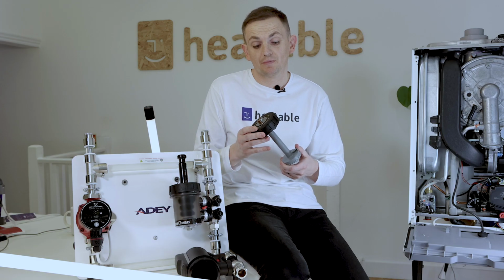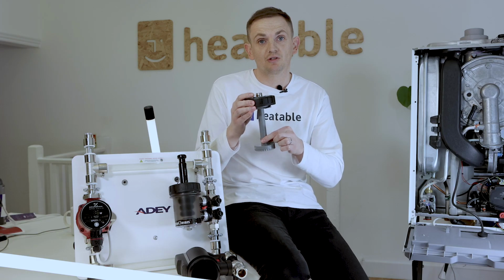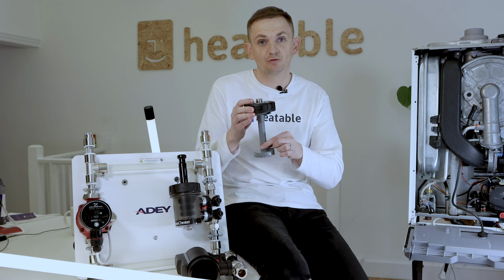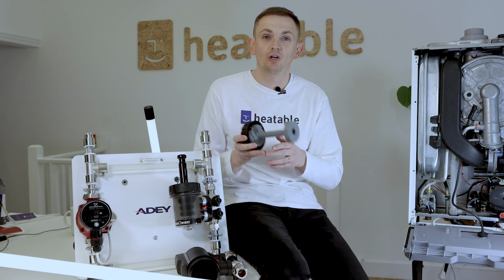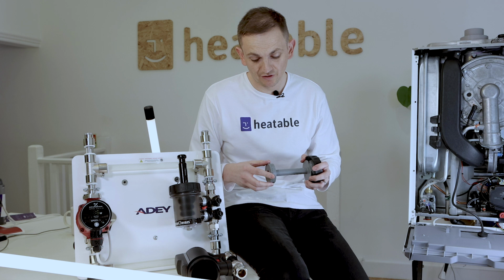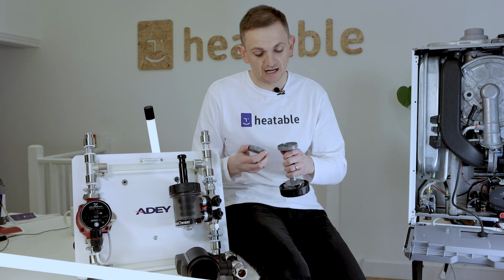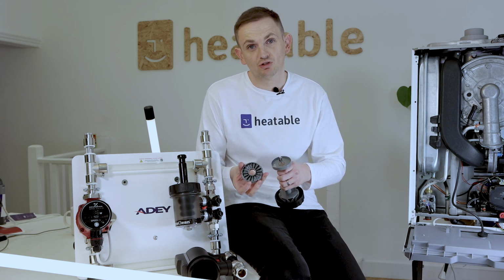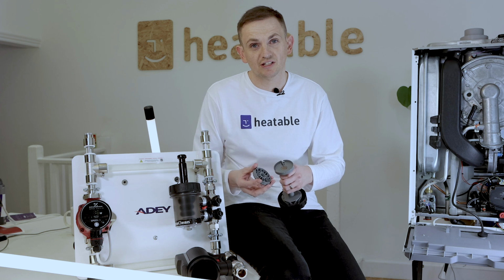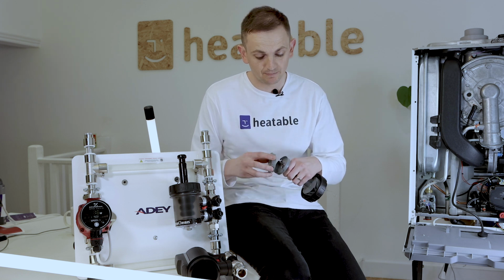Inside the filter, there's the magnet leg, which captures all the material that's running around the system. Also, on the ADEY filters that Heatable fit, there's an additional section which captures items such as flux or loose debris in the system that the magnet wouldn't attract.